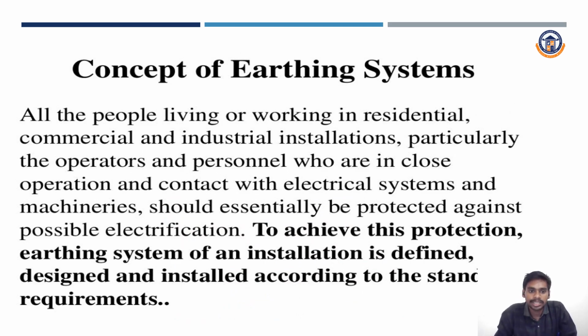Concept of earthing system. All the people living or working in residential, commercial, and industrial installations, particularly the operators and personnel who are in close operation and contact with electrical systems and machineries, should essentially be protected against possible electrification. To achieve this protection, the earthing system of an installation is defined, designed and installed according to the standard requirements.